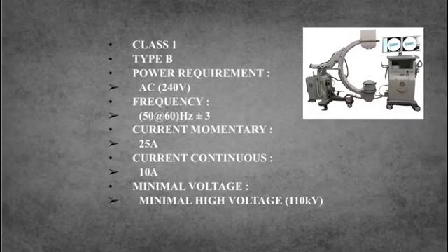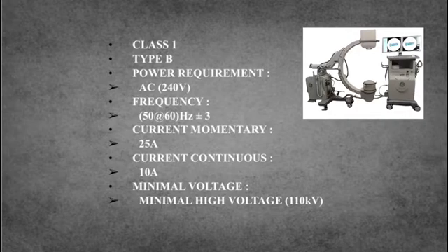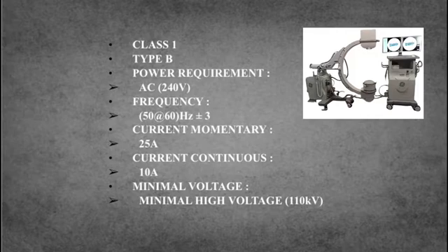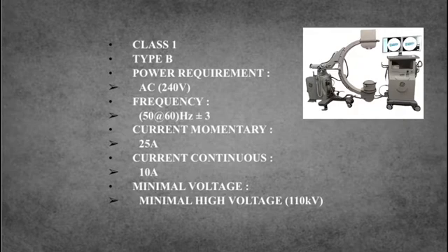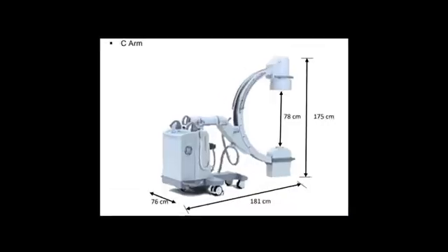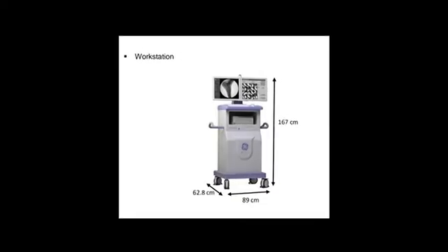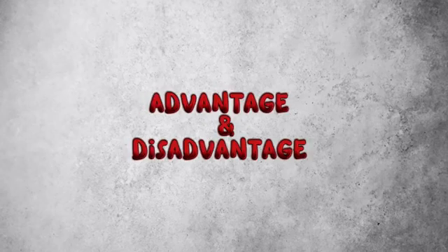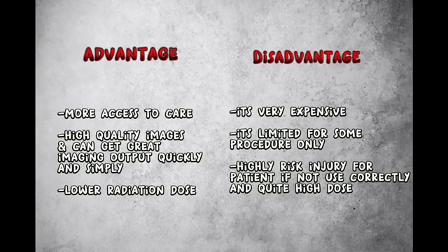Let me introduce the specification for this system device. This device is in class 1 and has type B. For power requirement, we use AC 240 volts and frequency at 50 or 60 hertz plus or minus 3 hertz. For the current, we use 25 ampere and current continuous 10 ampere. Lastly, for the x-ray tube, the minimum high voltage is 110 kV.